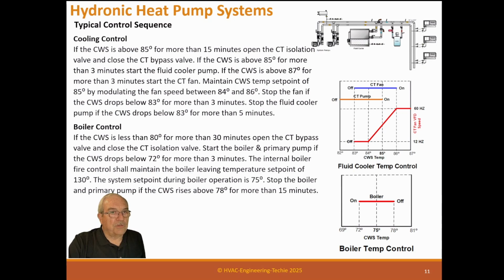And then we side stream to the boiler. So the hot water goes to the units, and it comes back, goes to the pumps, and comes right back and just goes to the boiler heating the water up. We don't have the fluid cooler in the mix. So here's its temperature. If the temperature gets to 72 degrees, it enables the boiler. The boiler comes on to fire, and it will adjust. The boiler fire control will control it, trying to maintain 75 degrees. If it gets above 78 degrees, then it will turn the boiler off. It'll disable the boiler. And this is a real simple boiler control.